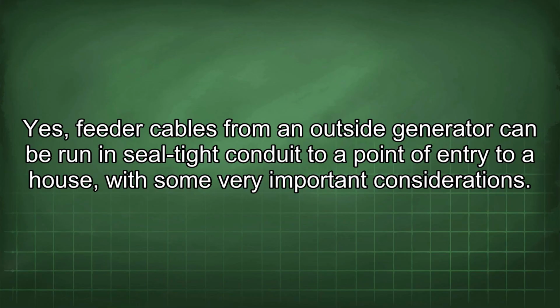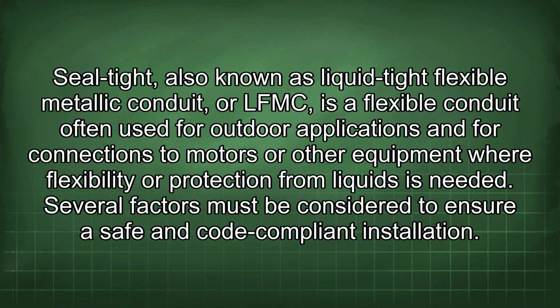Yes, feeder cables from an outside generator can be run in seal-tight conduit to a point of entry to a house, with some very important considerations. Seal-tight, also known as liquid-tight flexible metallic conduit, or LFMC, is a flexible conduit often used for outdoor applications and for connections to motors or other equipment where flexibility or protection from liquids is needed. Several factors must be considered to ensure a safe and code-compliant installation.